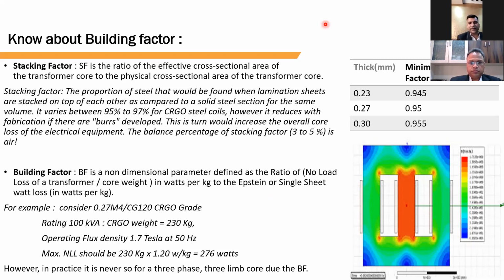So we are just taking a case of a 100 kVA transformer. Suppose the weight of that 100 kVA transformer core is 230 kg. And just for simple understanding, I am saying that the operating flux density of that transformer is 1.7 Tesla at 50 Hertz frequency. So our ideal no load loss should be the weight of the core into the watt loss at 1.7 Tesla. If we multiply 230 kg by 1.20 watts per kg, which is at 1.7 Tesla, then the ideal no load loss should be 276 watt. But in practice, this never happens. Why? Because we need to consider the building factor of that particular core also.